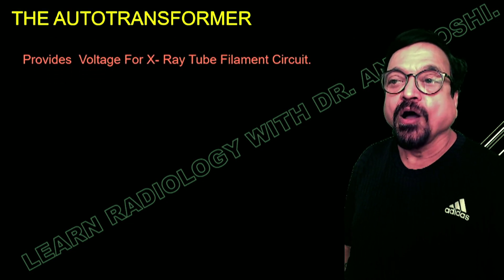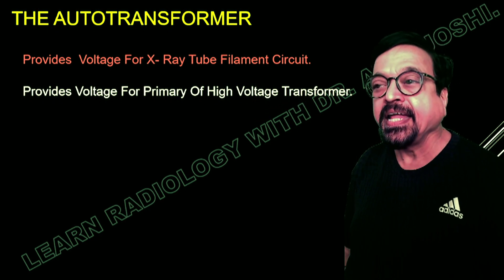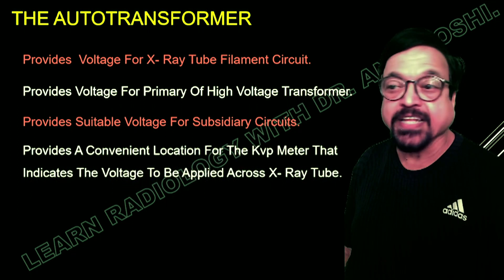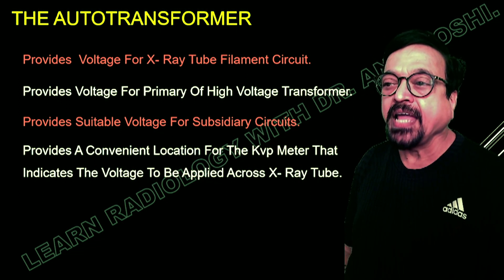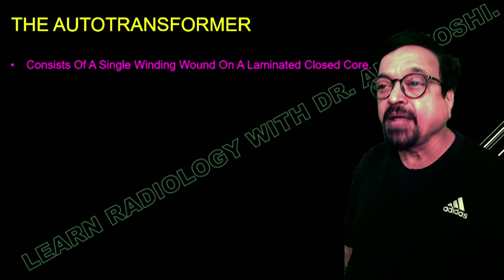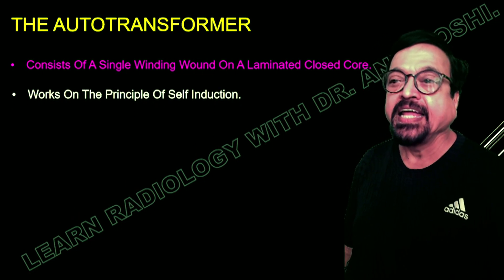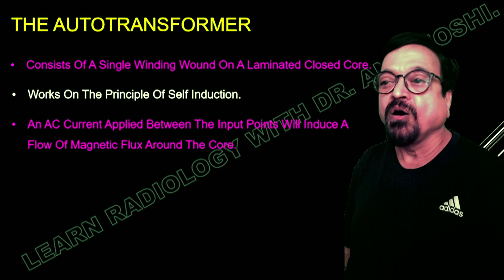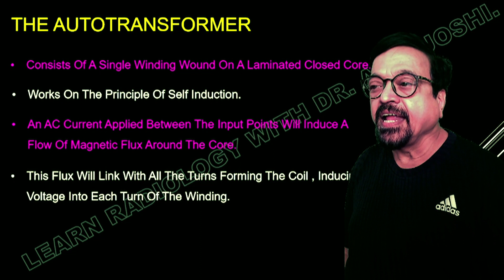The auto transformer provides voltage for the x-ray tube and filament circuit. It provides voltage for the primary of the high-voltage transformers, suitable voltage for subsidiary circuits in the x-ray unit, and a convenient location for the kVp meter indicating voltage to be applied across the x-ray tube. KV, mA, and seconds are the three factors required for radiography. The auto transformer consists of a single winding wound around a laminated closed core with insulation, working on the principle of self-induction. AC current applied induces a flow of magnetic flux around the core.